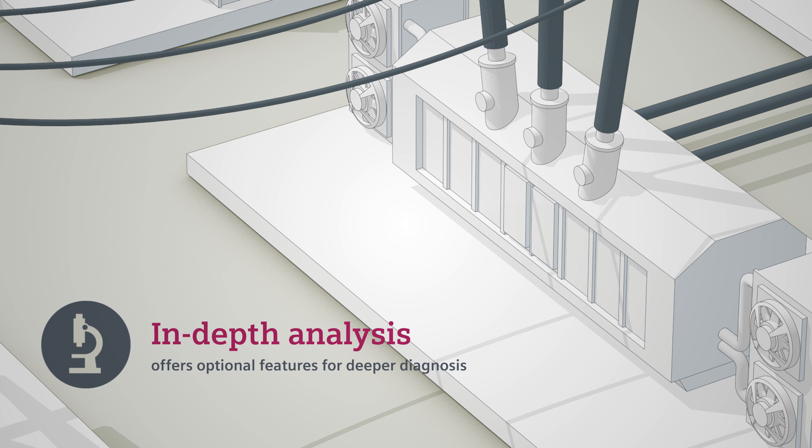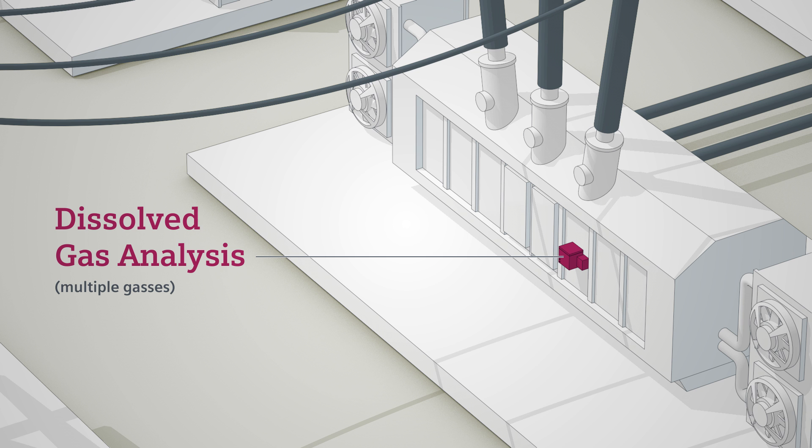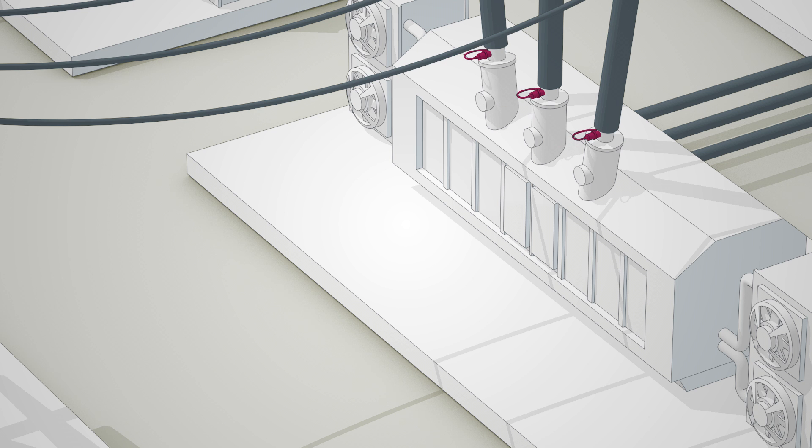If required, you can additionally focus on further details of your transformer's performance. This includes dissolved gas analysis for multiple gases, as well as bushing diagnostics, where sensors are directly attached to the bushing test taps.